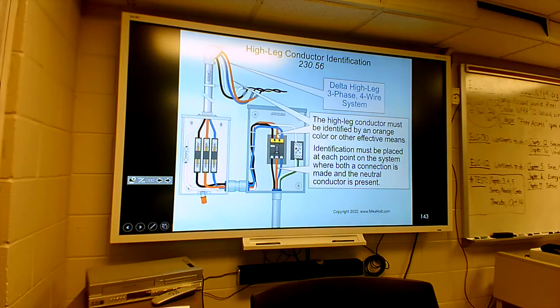The reason they call it a high leg is because if you take a voltmeter and measure from, say, the black wire, the first one, to neutral, it'll read 120. If you read from the blue wire to neutral, it'll read 120. If you read from the orange one to neutral, it'll read 208. You can't use the orange conductor on single phase receptacles and lights because it will actually burn up. You can't use the orange leg on regular receptacles and lights and things. It can only be used for motors.